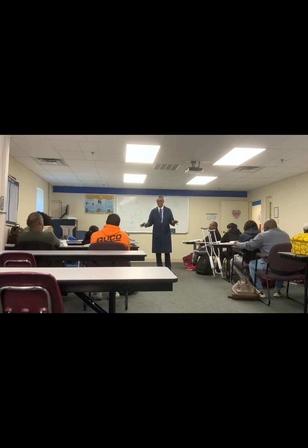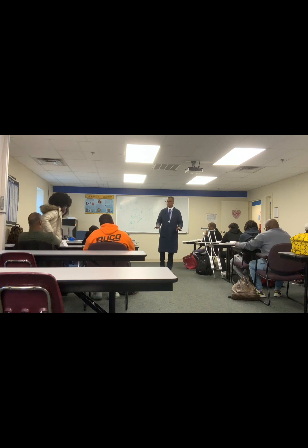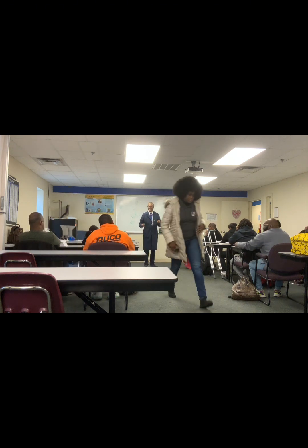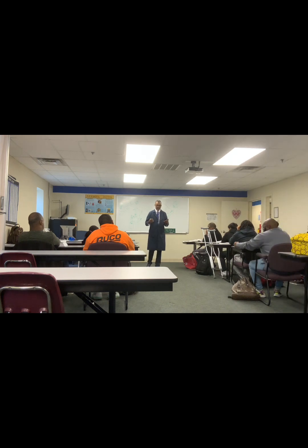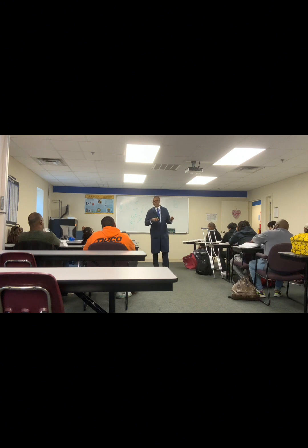You can zone a system different ways. We're talking residential. It's been in commercial for years. We can zone by having two systems, which is pretty common: one system upstairs, one system downstairs. So that's two zones, operating to create comfort air in two different areas with two different machines. You can also zone with a zone board. Say if I had a 2-ton and a 3-ton, I may put in a 4.5-ton that can carry the load of upstairs and downstairs if it were zoned. In this case, zoning would be dampers.